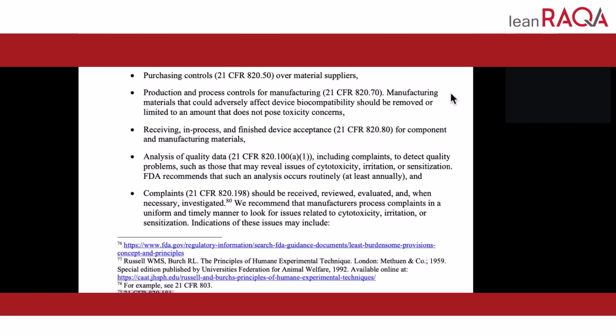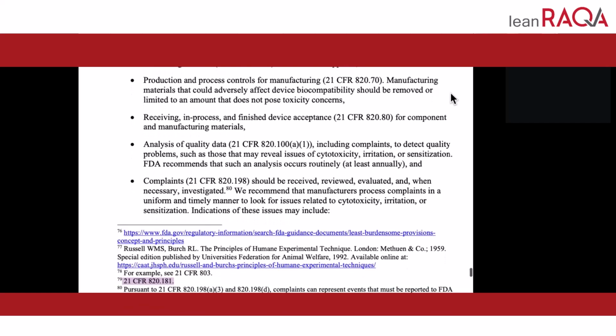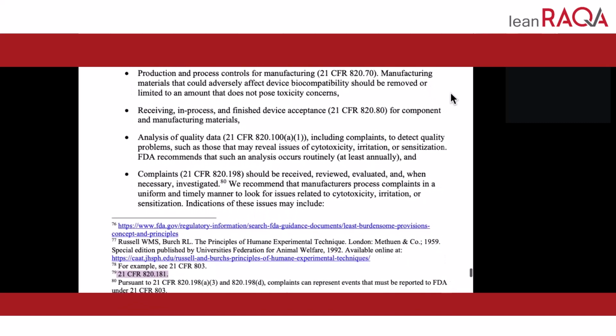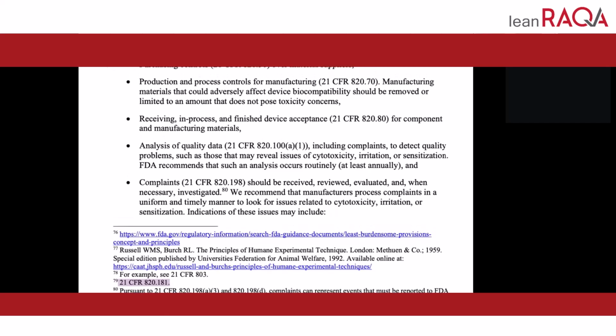Number two, production process controls. Temperature, humidity, time. Those are the basic things on molding. So all the plastics out there you can think of, they're all going to be temperature, pressure, and time. But you could have other factors too, like you can have post-cure. You could have some sort of coating that goes on. All kinds of things could be done to it. Every little step of that has to be documented, and you have to follow those procedures. And if it's automated, you have to validate it. And if you make any change in your manufacturing process, you have to assess what the impact is on biocompatibility. So, we have to follow production process controls.